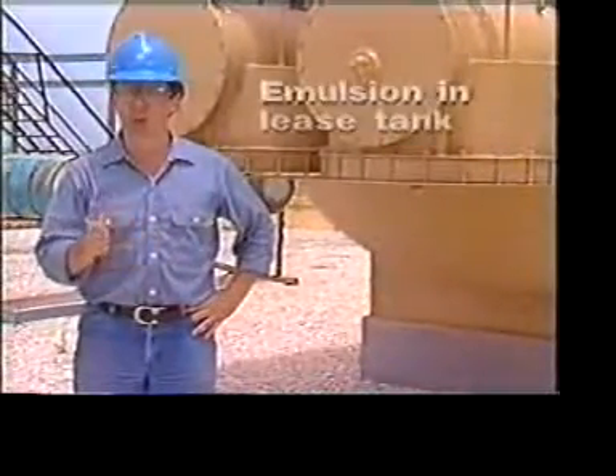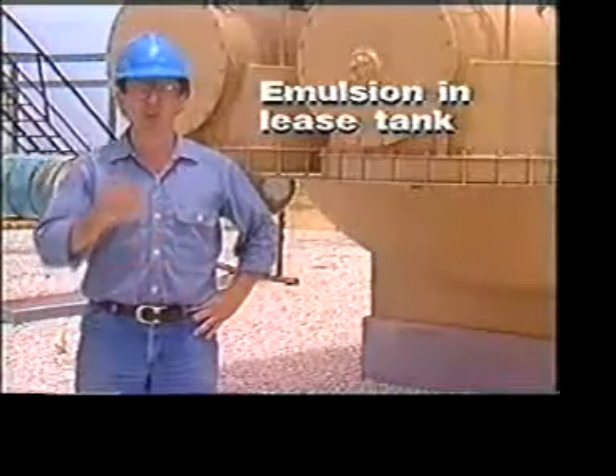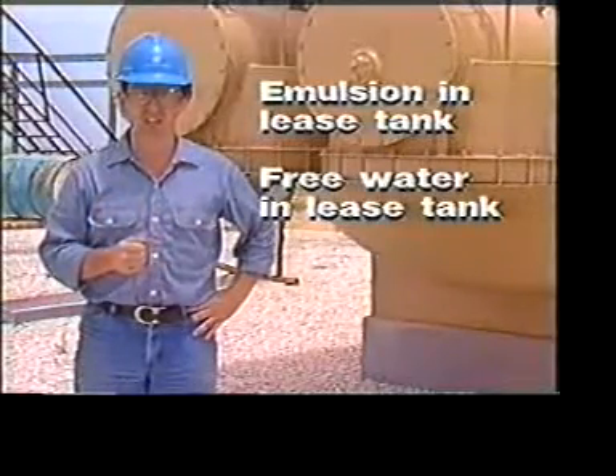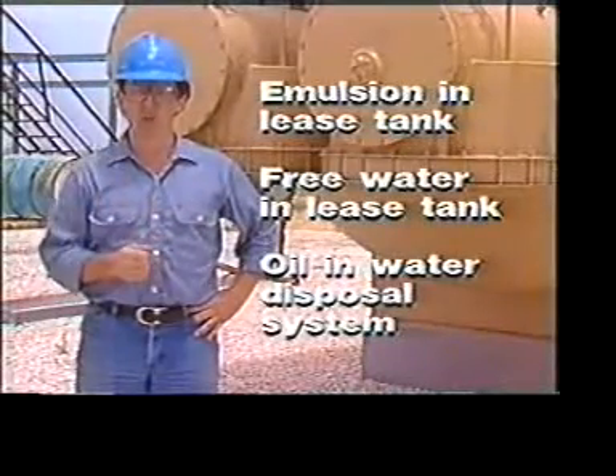No matter how carefully you think you've operated your treater, occasional problems will appear. Three of the more common problems are emulsion in the lease tank, free water in the lease tank, and oil in the water disposal system.